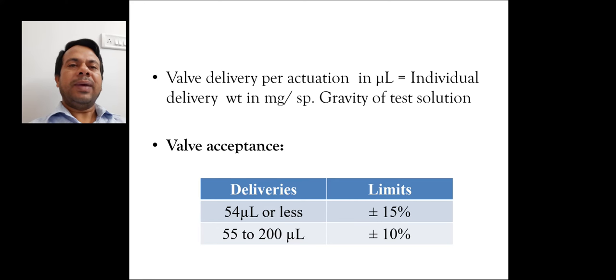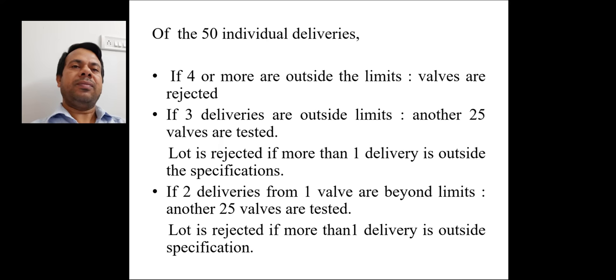Now the valve acceptance criteria. If the delivery of valve is 54 microliters or less then the acceptance limit is plus minus 15%. If the delivery is 55 to 200 microliters then the acceptance limit is plus minus 10%. Of that 50 individual deliveries, if 4 or more are outside the limits then valves are rejected.